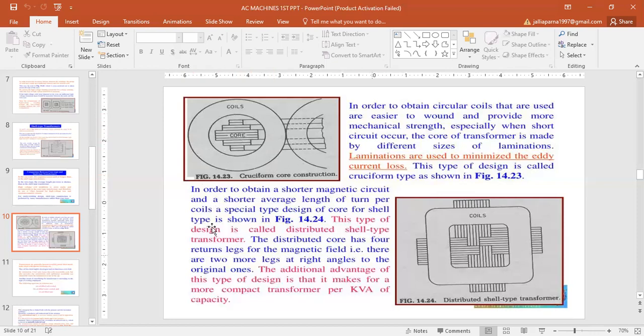So next one is the distributed shell type transformer. In order to obtain a shorter magnetic circuit and a shorter average length of turn per coil, a special type of design of core for shell type is used. This type of design is called distributed shell type transformer. The distributed core has 4 return legs for the magnetic field. That is, there are 2 more legs at right angles to the original ones. The additional advantage of this type of design is that it makes for a more compact transformer per kVA of capacity.